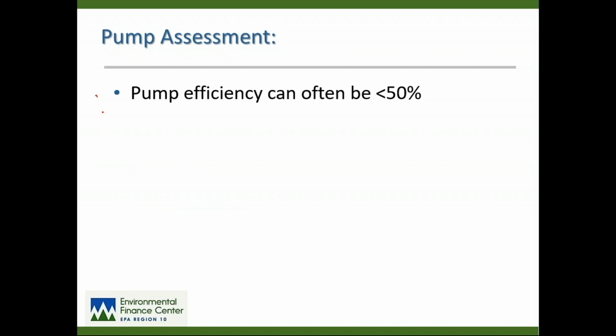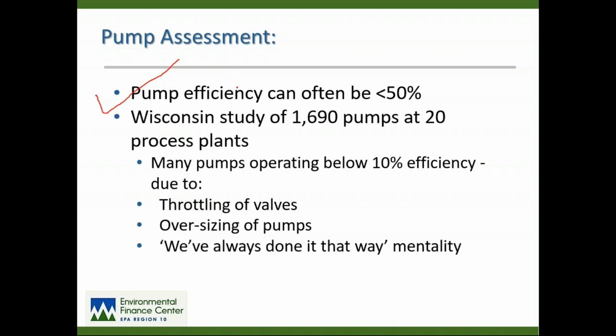When we go out to do an energy audit, we very often find pump efficiency less than 50%. And again, in terms of dollars and cents, that means less than 50 cents on the dollar in terms of work produced per dollar paid for energy. There was a study in Wisconsin quite a few years back now, probably at least 10 years. They went around and looked at almost 1,700 different pumps, large and small, at 20 different process plants, water and wastewater and food production and packing houses.